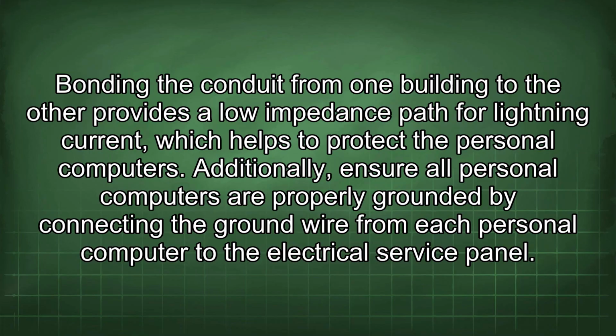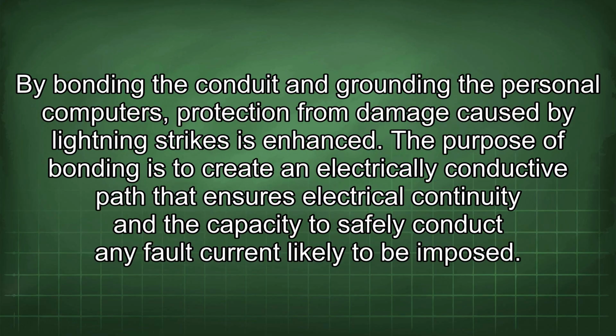Bonding the conduit from one building to the other provides a low impedance path for lightning current, which helps to protect the personal computers. Additionally, ensure all personal computers are properly grounded by connecting the ground wire from each personal computer to the electrical service panel. By bonding the conduit and grounding the personal computers, protection from damage caused by lightning strikes is enhanced.